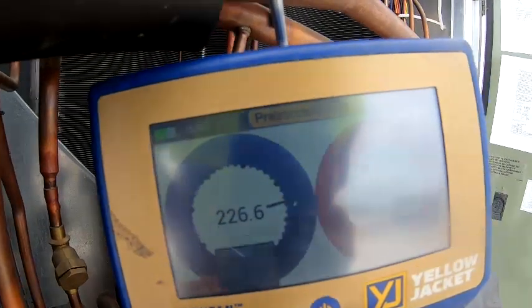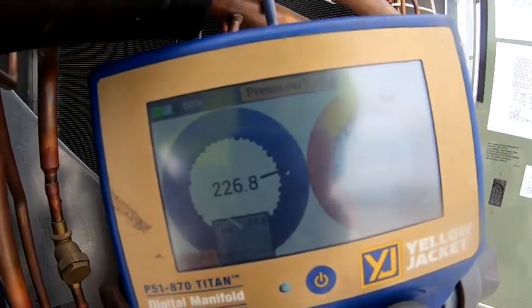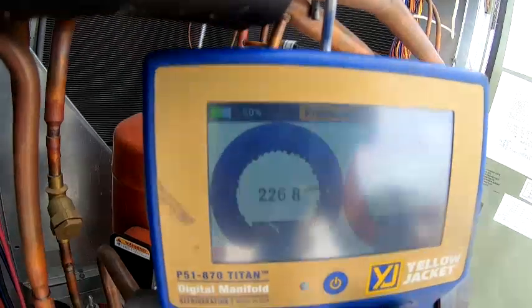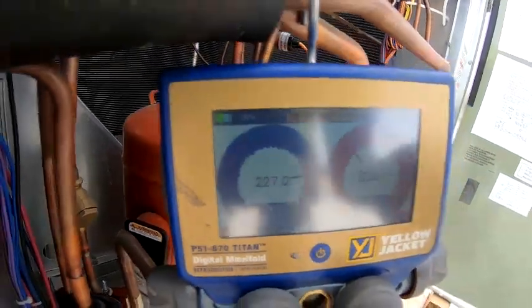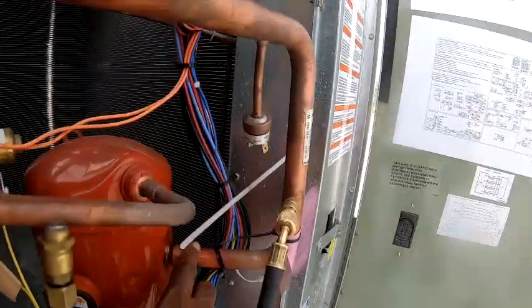So the thing about the soap bubbles though, if you only put maybe 5 to 10 PSI of nitrogen in there, it's like blowing slow. When you were a kid with the little round sticks, you'd dip it in the bubbles, and if you blow real fast, you can't make a bubble, but if you blow slowly, you can blow a big bubble. Same concept here: with 200 PSI or 100 PSI, it's like blowing fast, but if you put just a small amount in there, barely blowing, you'll get a big bubble.